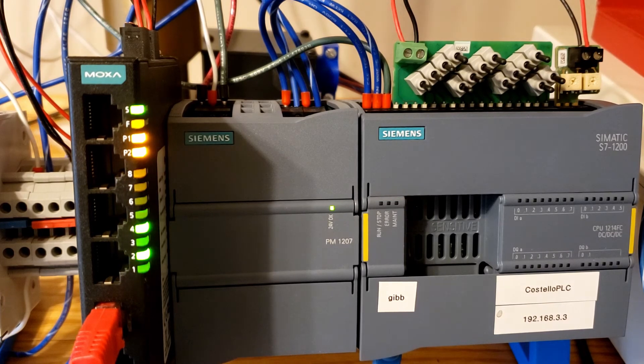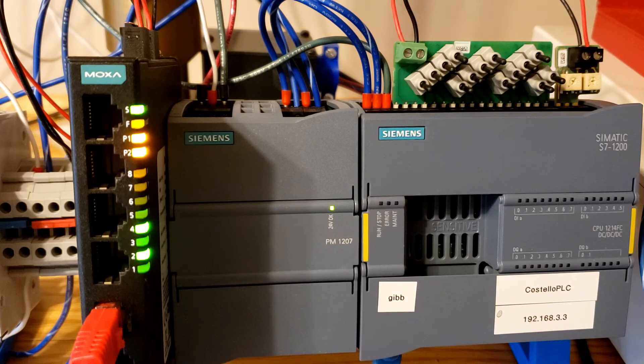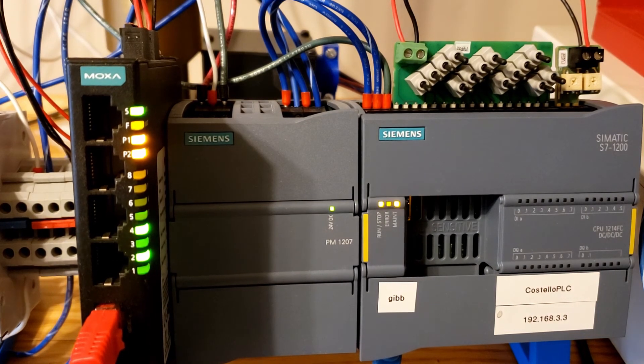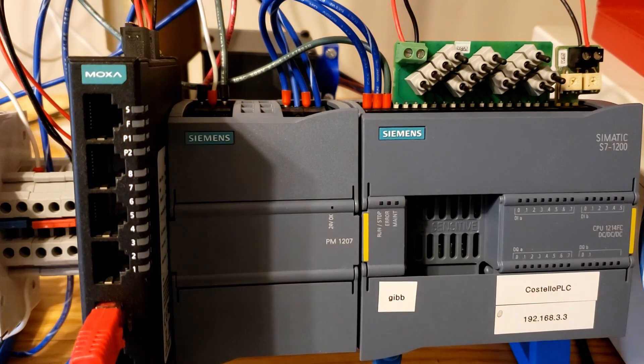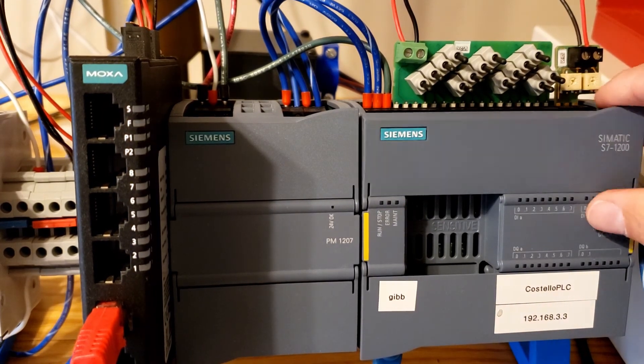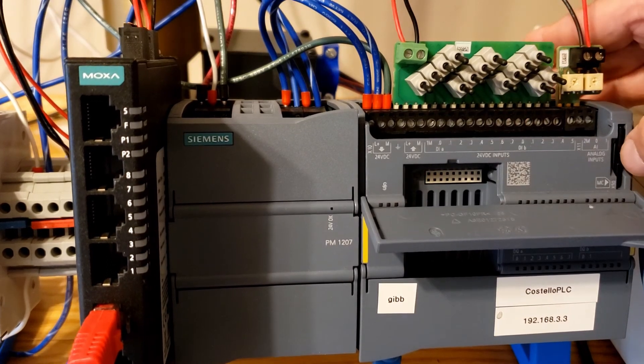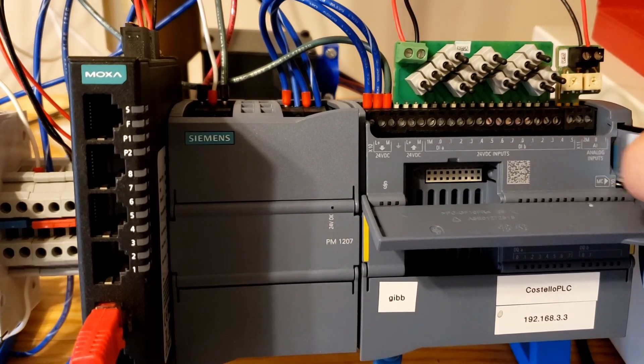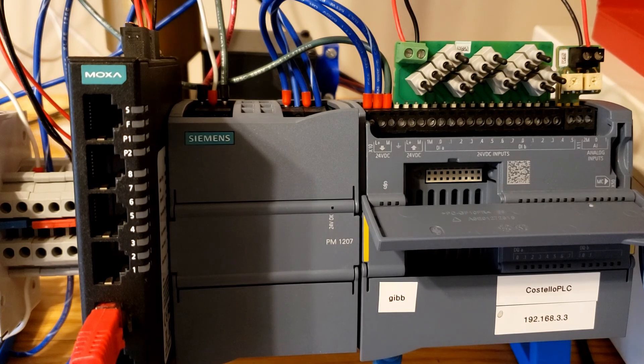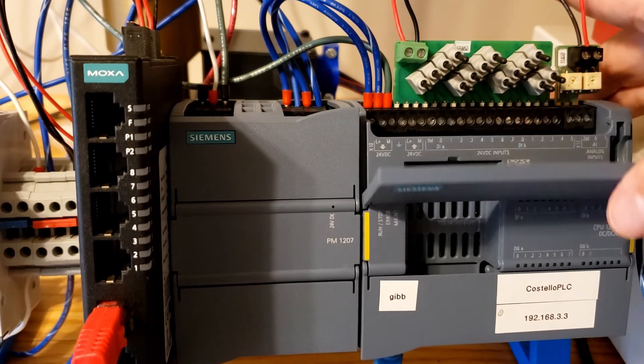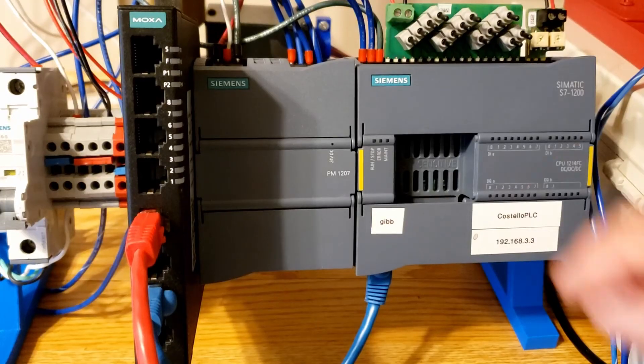Now it overwrites everything, so make sure that your hardware settings and everything were proper for that PLC. The lights start flashing yellow - that means it's done, but wait for it to finish before pulling the card out.